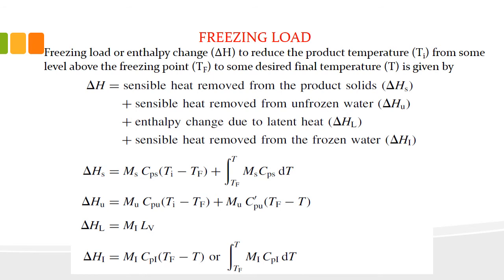So the freezing load is the sum of all these terms. That is sensible heat removed from the product solid, sensible heat removed from the unfrozen water, sensible heat removed from the frozen water, and the enthalpy change due to latent heat of crystallization.